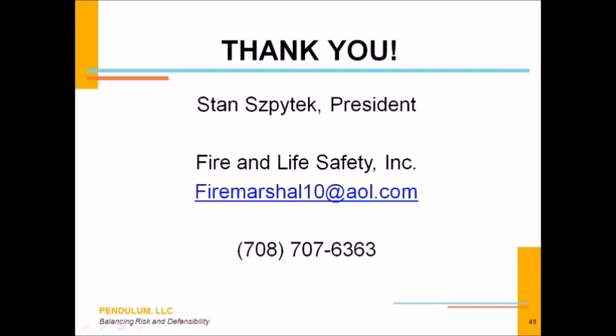Now, I didn't take the time today to show you all the pictures that I like to show when I do a live workshop. But again, going back to my roots as a firefighter, or anybody that's had an experience with a fire, we know that a closed door is the difference between life or death. And there are certain tolerances within that door that sits within a door frame that are allowable. For example, you're only allowed to have an eighth of an inch gap around the three parts of the door that sit into that frame. Those are the sides and the top. And in general, the undercut of that door can be no more than 3/4 of an inch.